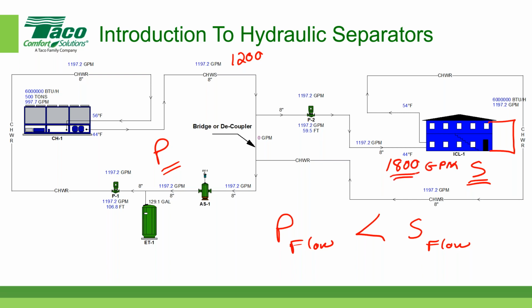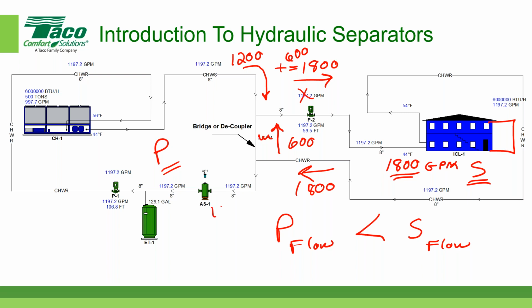Well, how could I get 1,800 out of 1,200? Well, 1,200 comes around the corner, and I'm peeling off 1,800, not 1,200 anymore. I'm peeling off 1,800 gallons per minute. That means that flow across the bridge is now in the opposite direction, and that's going to be 600 gallons per minute. So there's 1,200 plus 600, let me write that up there, equals 1,800. That's a little goofy, I know, but you get the general idea. And then as that 1,800 gallons per minute comes back toward the primary circuit, we're going to peel off 600, and so what returns back is 1,200.